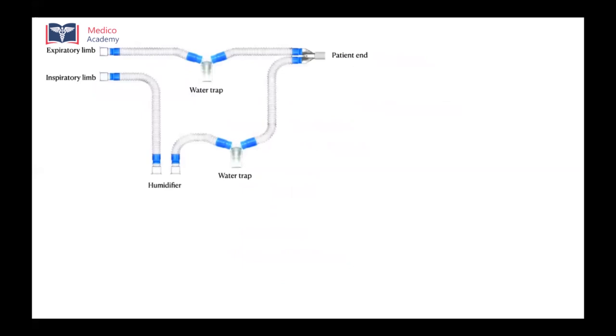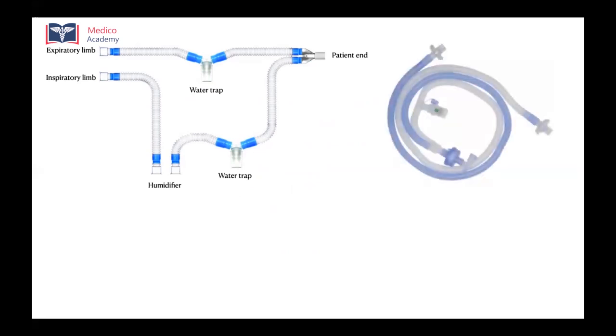So these are the various connections that you usually find in a ventilator circuit. There'll be an inspiratory limb and an expiratory limb. An inspiratory limb will go to a humidifier, which will humidify the inspired gases. There'll sometimes be water traps, and many of the new circuits don't come with water traps. Both the inspiratory and expiratory limbs will go to a Y piece, and it will be connected to the patient. So this is a modern circuit, which is a disposable lightweight circuit, where you can see the inspiratory and expiratory ends both have bacterial filters. In between, you can see a nebulizer. And then at the patient end, in the middle, you can also see an HME.